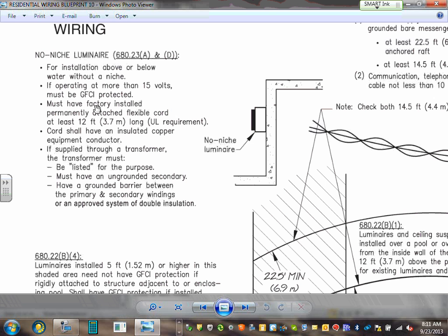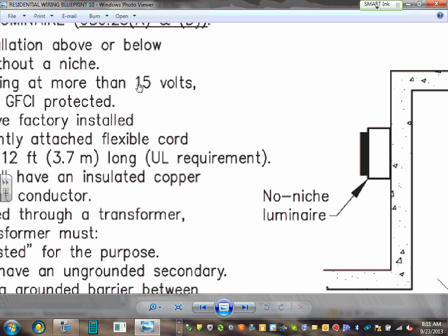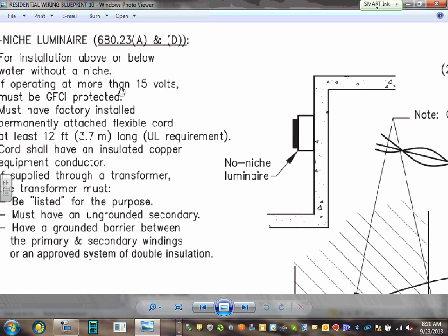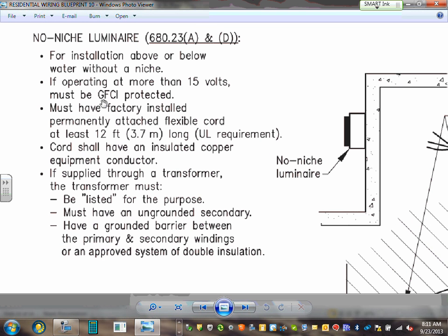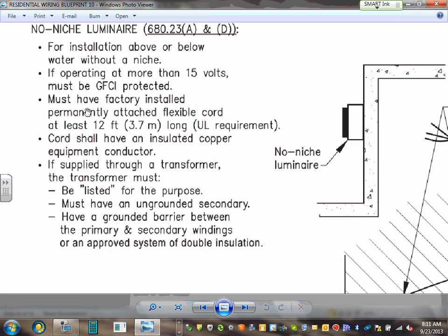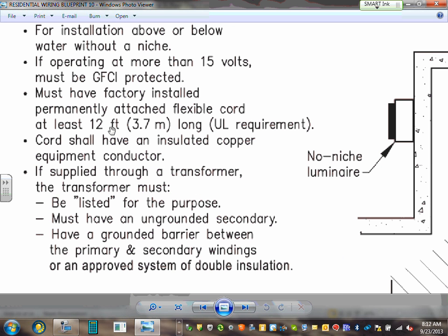Okay, so if you have a no-niche luminaire for installation above or below water, look at this, the voltage that you can run. Can you guys see the voltage? What voltage? 15 volt. Why do you think 15 volt? Safety inside the water. Must be GFCI protected. Must have a factory installed permanently attached cord at least 12 foot long. Why do you think you need a 12 foot long cord with it? You need to be able to take it out and maintain it, right?